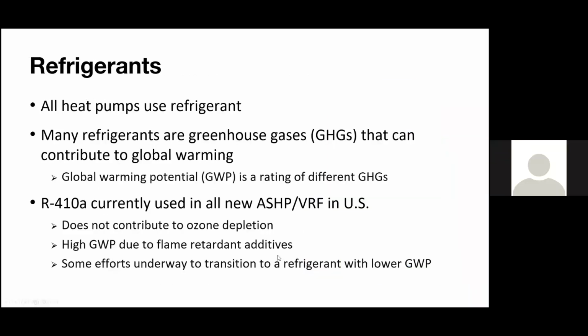So before I pass it off to Jason, I'm just going to touch a little bit on refrigerants. It is a very hot topic these days. Any refrigerant cycle, any refrigerant system, any piece of air conditioning essentially uses refrigerants. So all these systems we're talking about, whether it's an air source heat pump, water source heat pump, or ground source heat pump, all use refrigerants. Now we had refrigerants, I think the first one was Freon back in the 30s. We eventually figured out in the 80s that those refrigerants contain chlorine, and when they get up in the stratosphere they get broken up by the sun's rays.